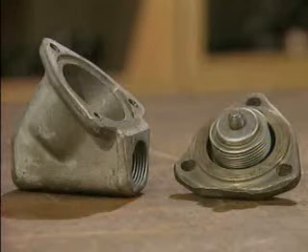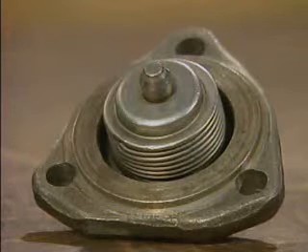A disadvantage of a bellows trap is that it generally can't be used in situations where pressures are very high because the bellows might collapse. Another disadvantage is that water hammer can rupture the bellows and cause the trap to fail.